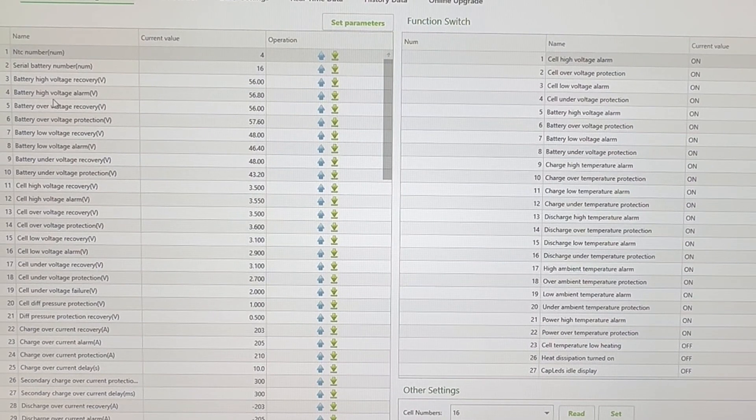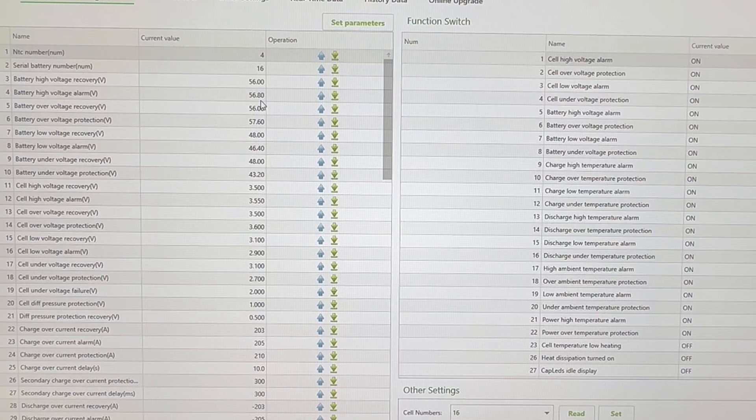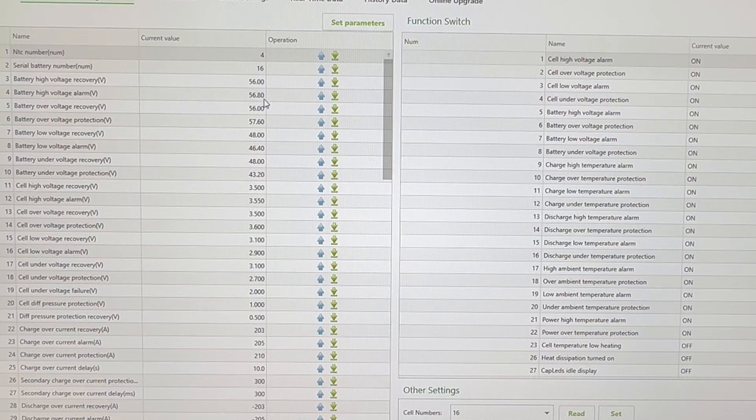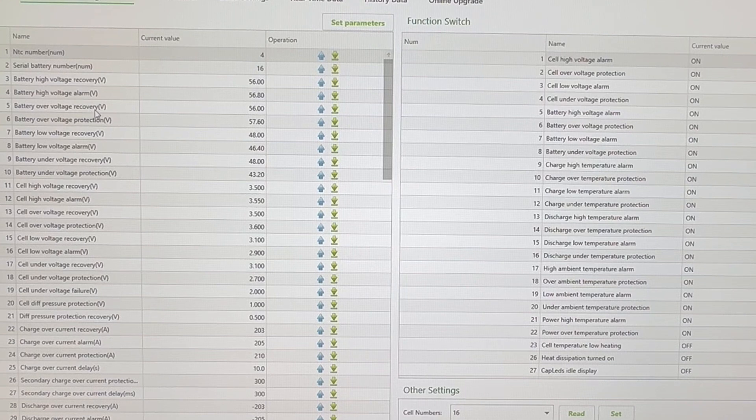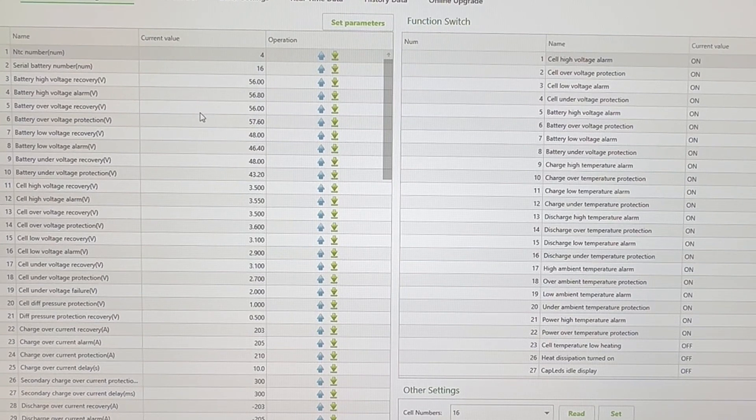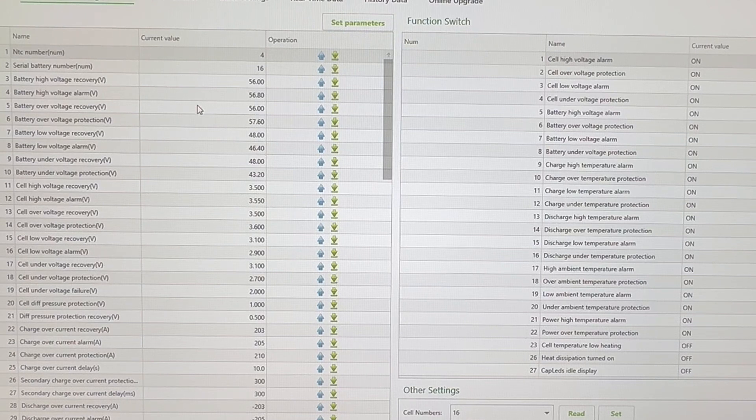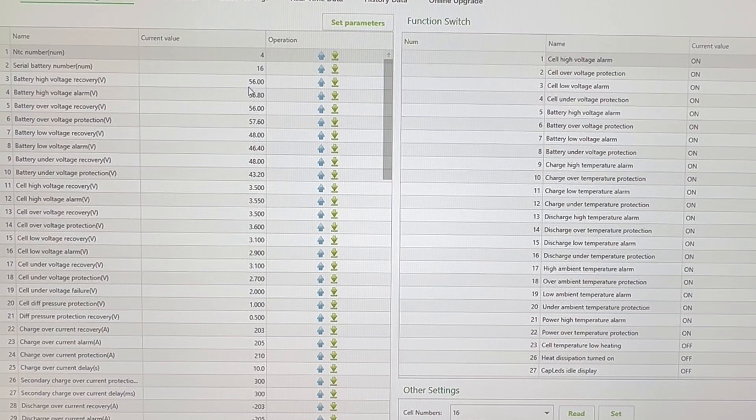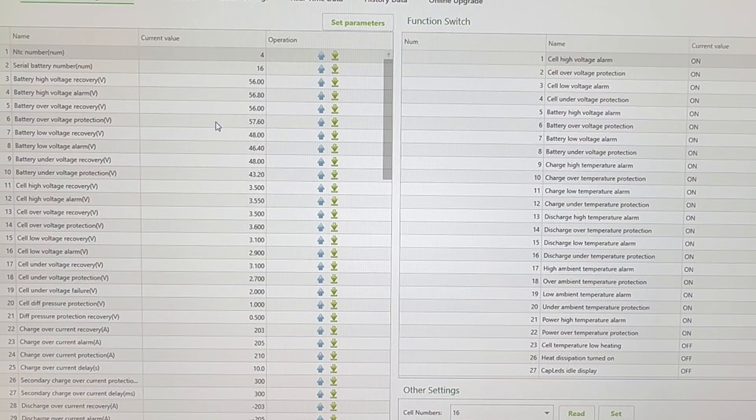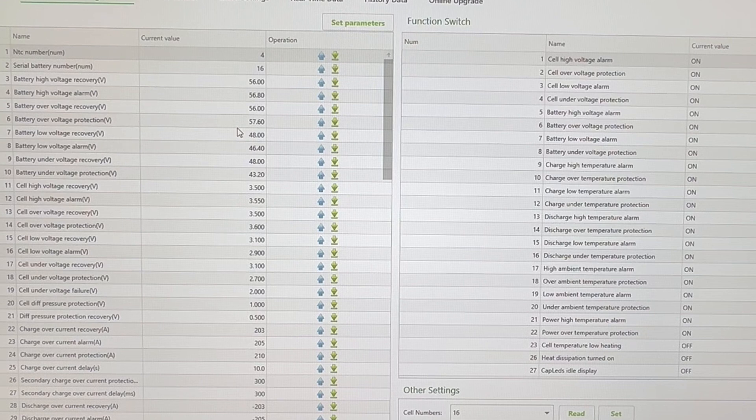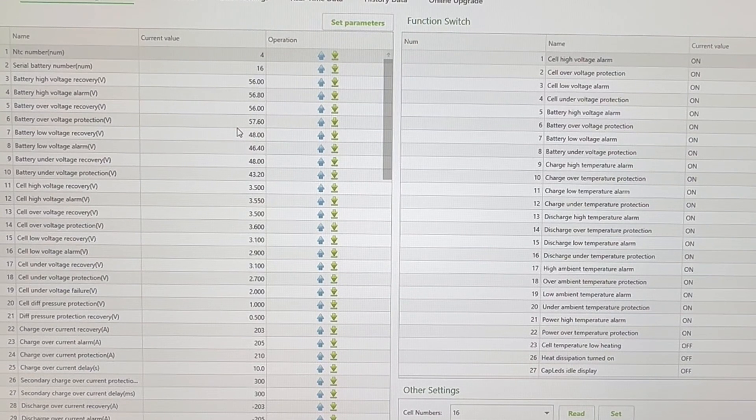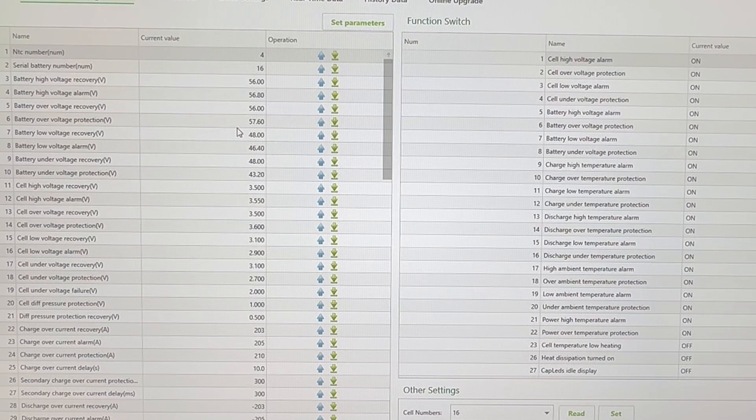Your battery high voltage alarm will be 56.8, and you'll see in a little while why that's going to be the case. Your battery over voltage recovery here, that's going to be set at 56. So lines 3 and 5 are going to be the same—they're a mirror of each other. They're a mirror of each other on the default settings, so if you changed one, you're going to need to change the other to match it. Line 6 is battery over voltage protection, which is 57.6 volts. Now that was actually the default setting.